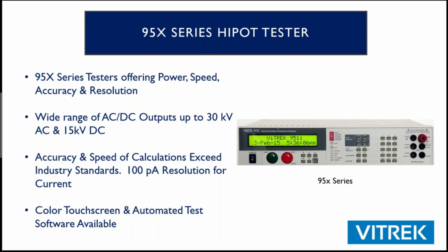And the answer is because sometimes you want to know these subtle differences, especially when you're trying to qualify new components, maybe changing line filters, changing printed circuit boards within the unit. And you want to be able to see these small differences. Did you just make your product better, worse, or was there no change? And with a less accurate product, you can definitely do the go, no-go testing, but you might not have the visibility into your product, and you might not find out that you have a serious issue until it's too late, and when you have an entire batch that's failing. And no one wants to be in that situation.